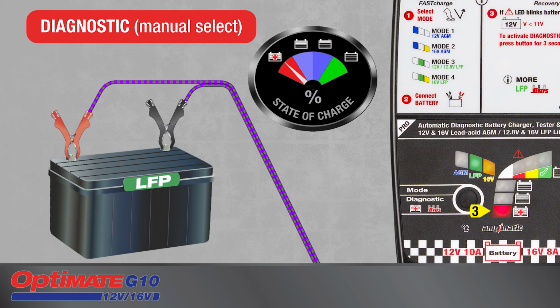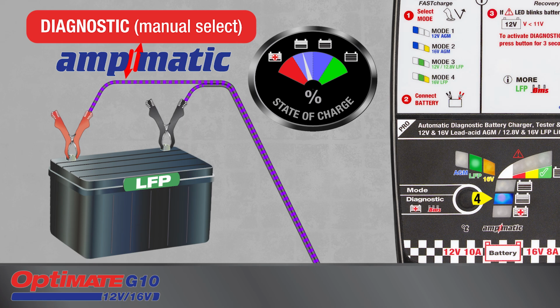A lithium LFP battery will receive a controlled recovery charge that will increase in power if the battery is recovering as expected. Progress is carefully monitored, charging may be interrupted, and error LED 3 will rapidly blink if permanent damage has been sensed. Blue LED 4 indicates the battery is more than 50% charged and is receiving Ampmatic controlled charge current that matches the battery's amp-hour capacity.